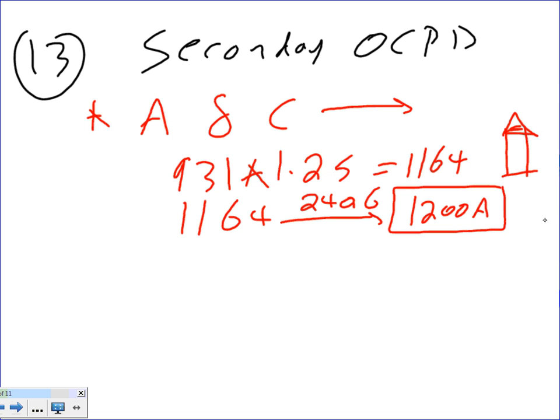How many of them, guys? Two. Why two? Because of the two phases. Two 1200 amp fuses or circuit breakers. It doesn't matter if it's a fuse or circuit breaker in this case, the calculation is still the same. While you guys are writing, I'm going to do phase B because it's just repetitive.